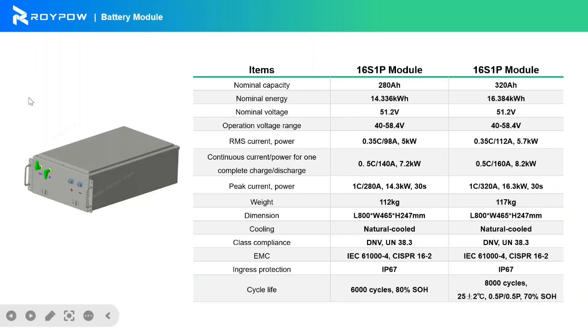Okay, let's move to the battery modules of this system. We have two modules. The first one is the 14 kilowatt-hour module, and the other is 16 kilowatt-hour. They have very similar weight and the same dimensions, but this one has a larger energy density. The cycle life is from 6,000 to 8,000 cycles, and the peak current is about 1 C, and the continuous is about 0.5 C.